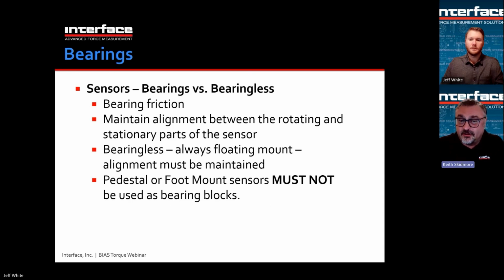Also, one of the things with bearing style sensors that happens is the bearings wear out. Now, if the proper couplings are used and they're used within their RPM ratings, they should last a very long time. But in many cases, there may be some kind of extraneous loading. Maybe the couplings aren't perfect. There are other types of couplings that we didn't talk about that are less desirable, rubber type couplings and things that do create some bearing loads. So the bearings can wear out. Bearingless, clearly you're not going to wear the bearings out. There are no bearings. They always are floating mount because, again, the sensor is only supported by its end connections. There's no housing with bearings supporting it. And that's it.